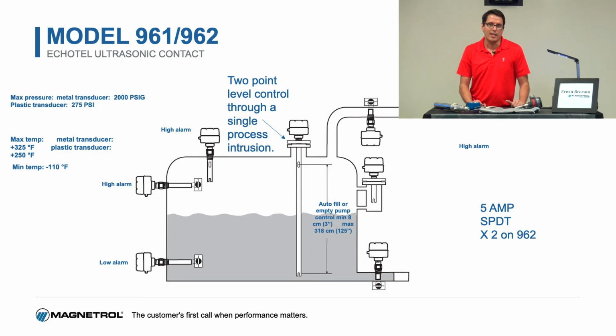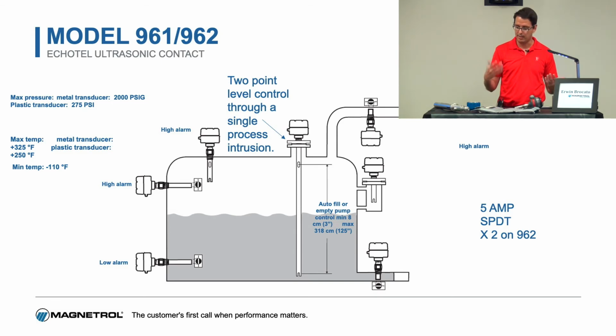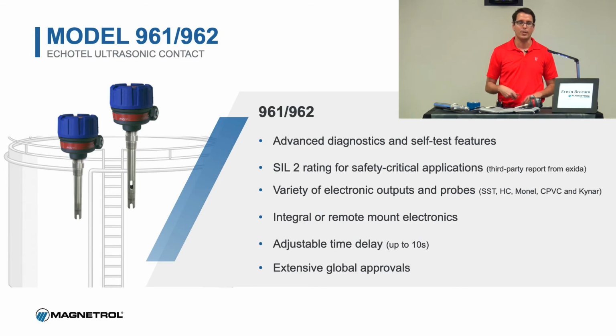Also, another interesting thing that you can do with this device, you can kind of simulate a flow switch. We have a flow switch actually, but in a certain diameter pipe, if your level goes below a certain point, that means it could be a low flow condition, and this switch can detect a low level in the pipe that is proportional to a low flow. So you can put it before a pump to protect your pump from cavitating, or it'll at least turn the pump off if it begins to cavitate because you have a low flow condition. So that's another pretty cool little application that you can do. Obviously we have flow switches, those are better, but they're not part of this presentation.